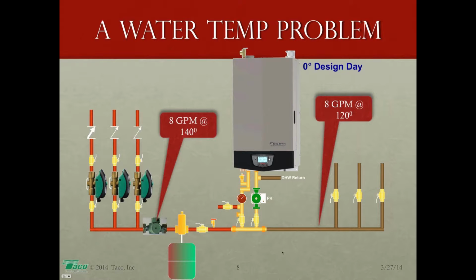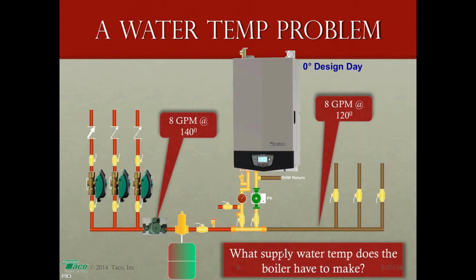Now, I have to figure out what supply water temperature the boiler should be making. What do I have to set that boiler's target temperature to under design conditions? I'll tell you right now, it's not going to be 140, because if I have this boiler make 140-degree water, I don't think it's going to work real good, as we will see. But that's the question I have for you. What water temperature should the boiler be making? Well, there's a couple ways to figure this out. I'm going to show you the hard way, then I'll show you a shortcut. Let's take a look.